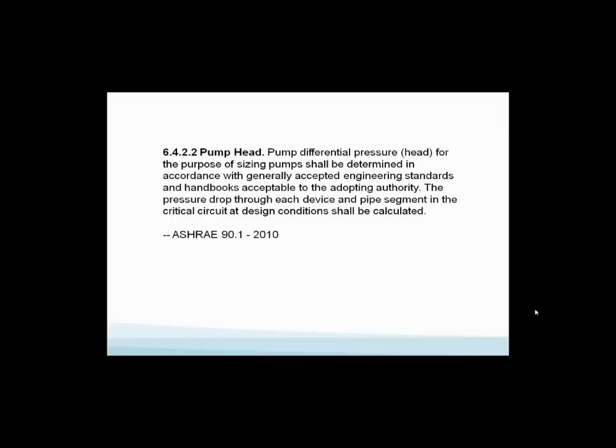This is an ASHRAE 90.1 2010 standard that DOE says is going to become energy code in every state. It's coming. Some states are there, some will be there shortly. It says the pump differential pressure head for the purpose of sizing pumps shall be determined - you have to do a detailed pump head loss calculation with all the fittings, all the devices for the critical circuit, for the critical path. You've got to do that calculation and put it in the file. We have to do a pump head loss calculation in detail and put it in your job file. That is new. No more guessing, no more just taking a stab at it.